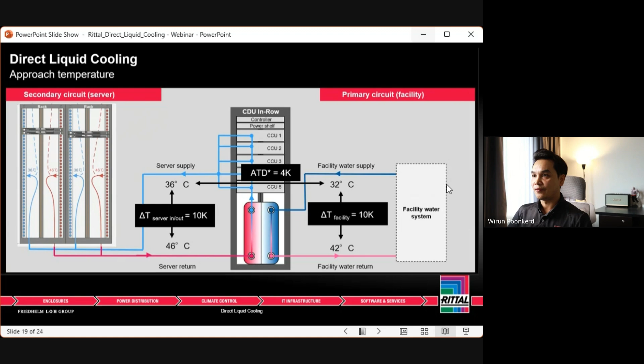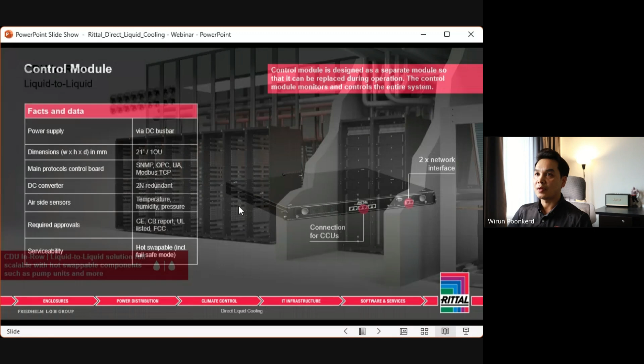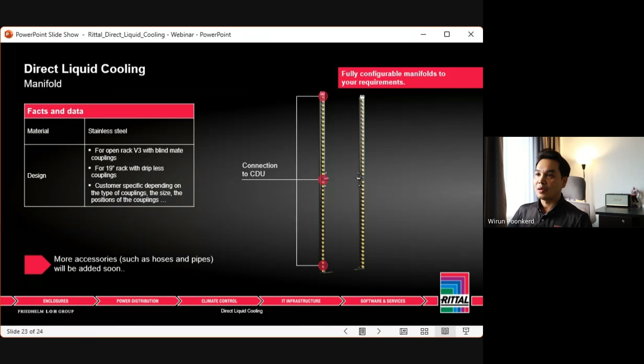Okay. So actually, for direct liquid cooling, we have the circuit following this picture. We have no special requirement for cooling; it can go up to 32 degrees for the facility water supply. Yes, this one is a control module. We can design the control module as N+1 also. Yes, accessories also. This one we can customize by customer requirement also.